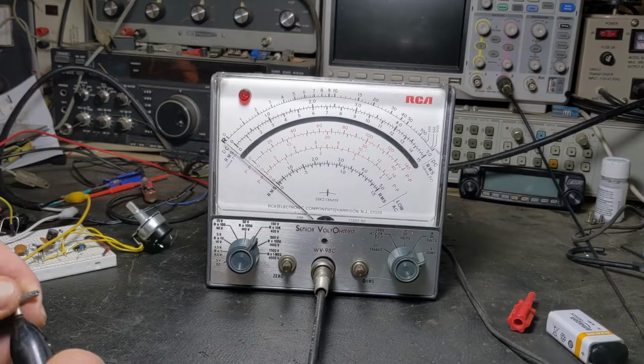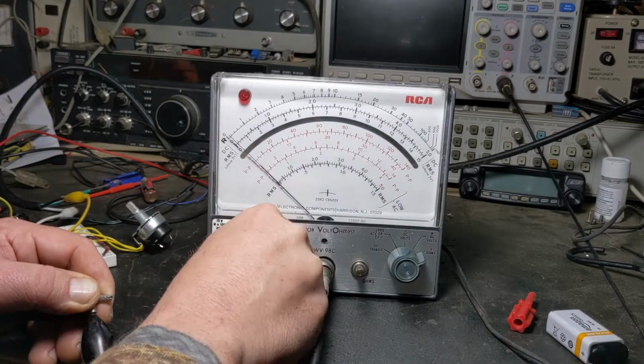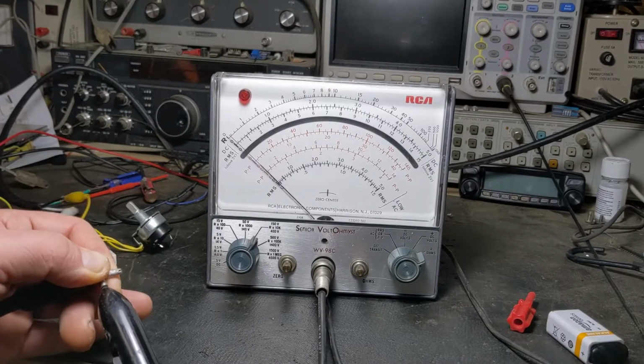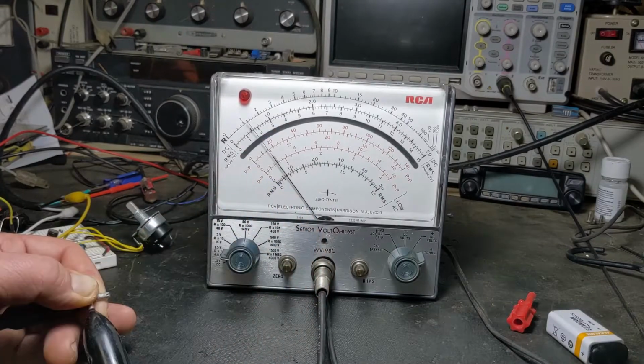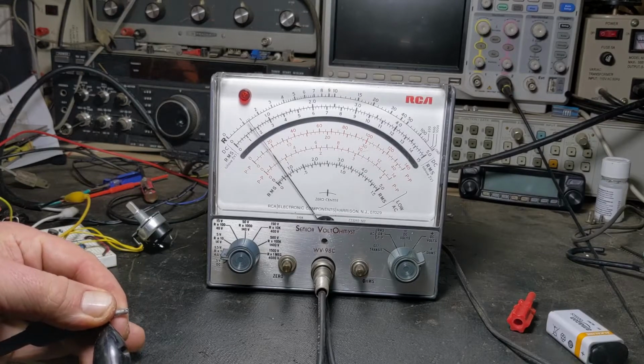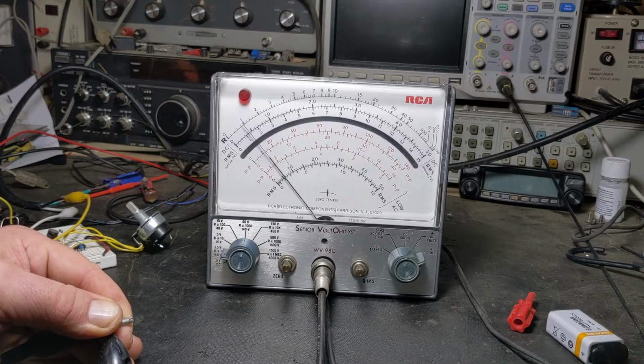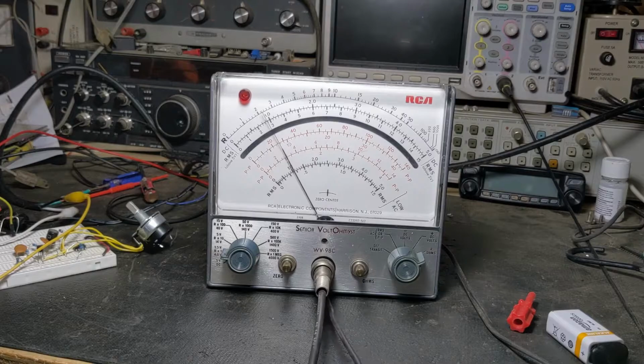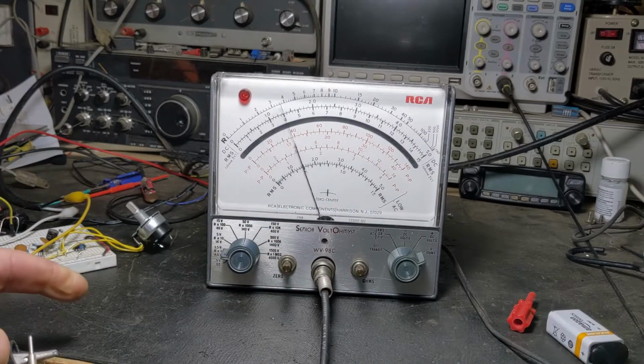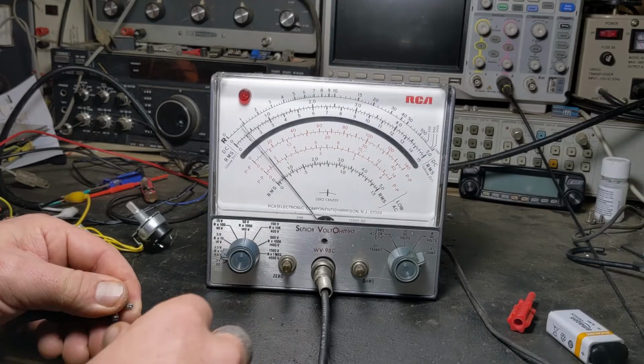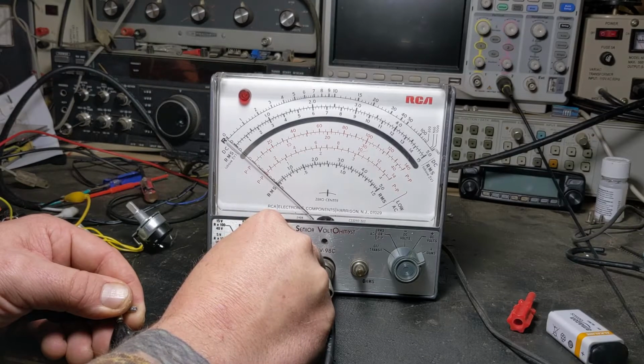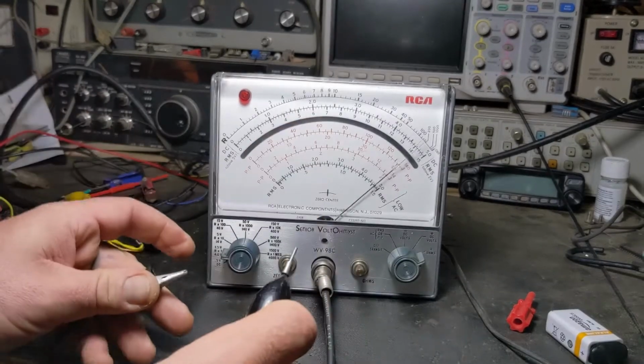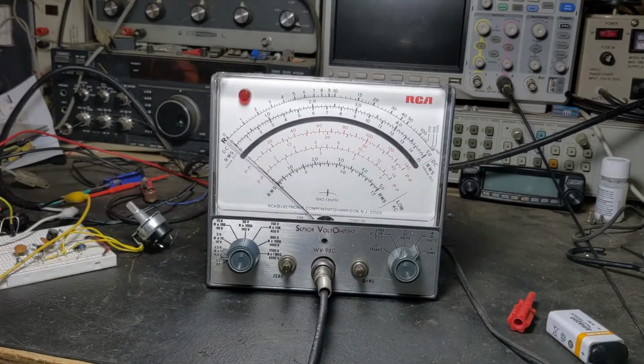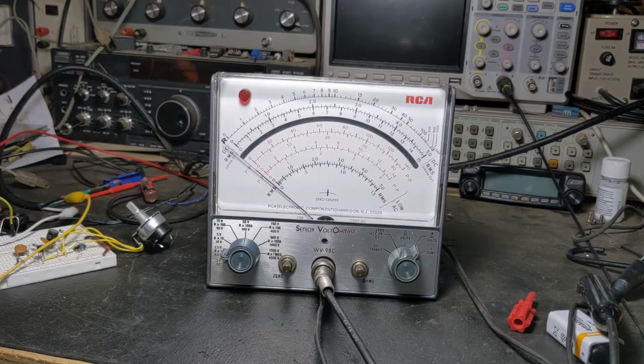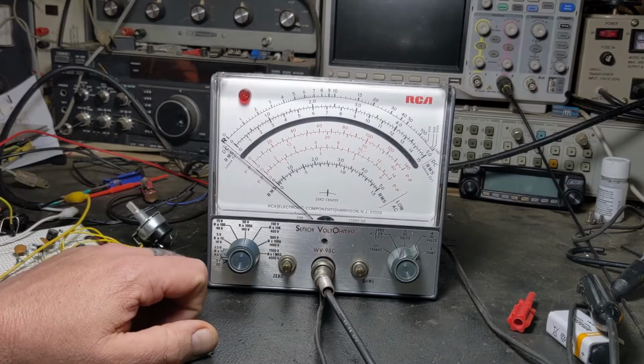And I like to just do this, because if you go to DC volts and then go back, see, we're reading right now, it's reading properly. If I come down, it should go up. See that? It's going to infinity. And we're getting a little over about 1 ohm. It's reading the resistance through all this here, and you see as I move this, this ain't perfectly set right here. And I'm touching it and all that. But if I zero it out here, I zero out this wiring here so I get a more true reading when I'm measuring something. So, anyway, that went a little longer than I thought it would, but we went through it and got it. So, there is the adjustments and calibration on this RCA WV-98C.